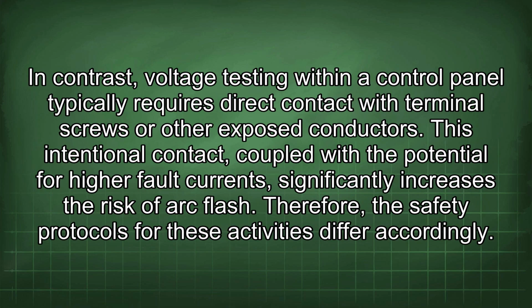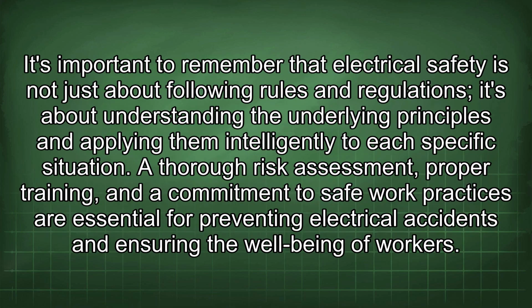In contrast, voltage testing within a control panel typically requires direct contact with terminal screws or other exposed conductors. This intentional contact, coupled with the potential for higher fault currents, significantly increases the risk of arc flash. Therefore, the safety protocols for these activities differ accordingly. It's important to remember that electrical safety is not just about following rules and regulations, it's about understanding the underlying principles and applying them intelligently to each specific situation. A thorough risk assessment, proper training, and a commitment to safe work practices are essential for preventing electrical accidents and ensuring the well-being of workers.